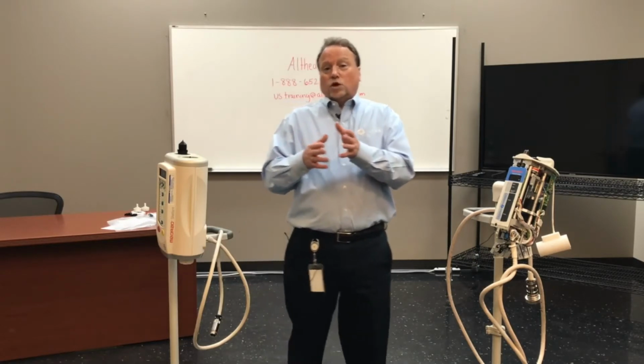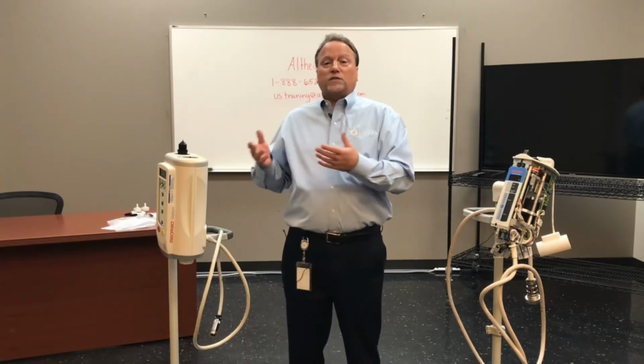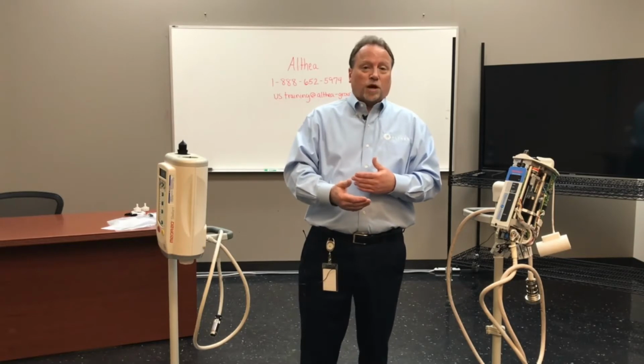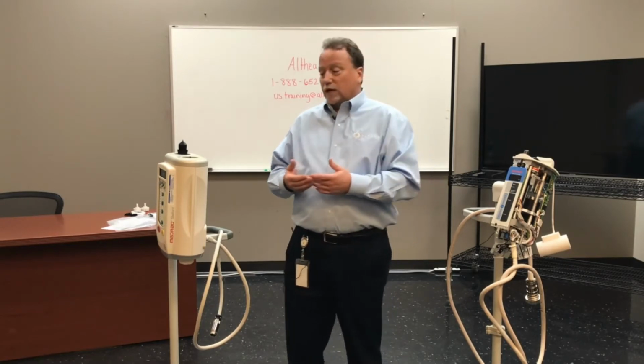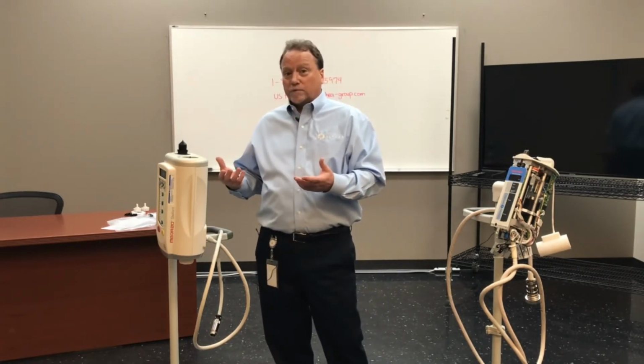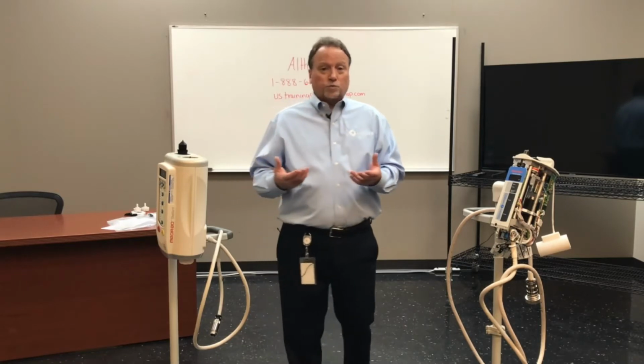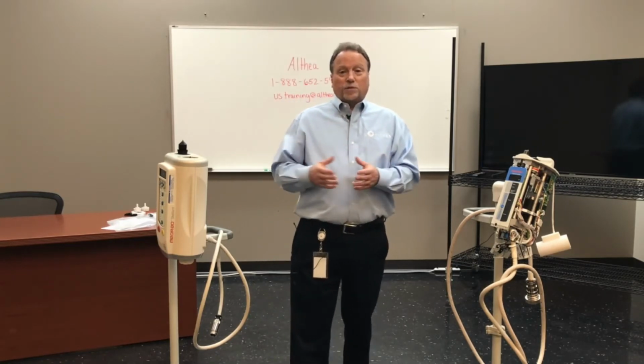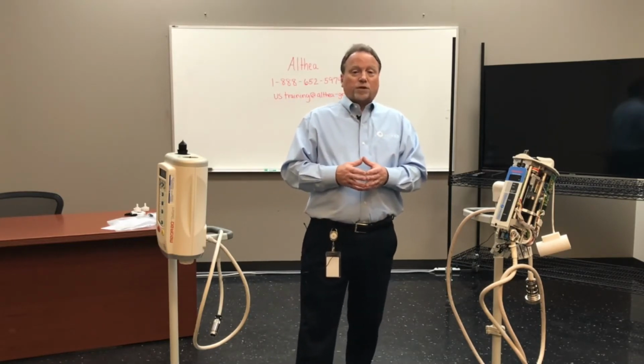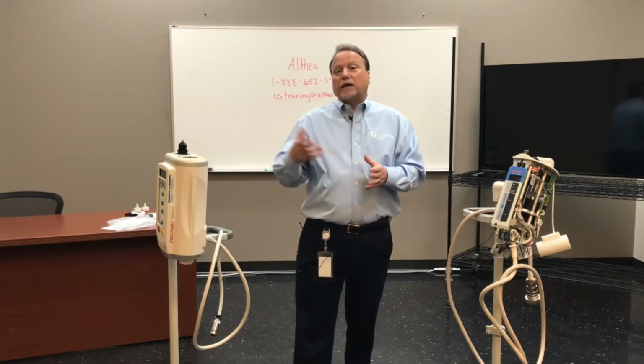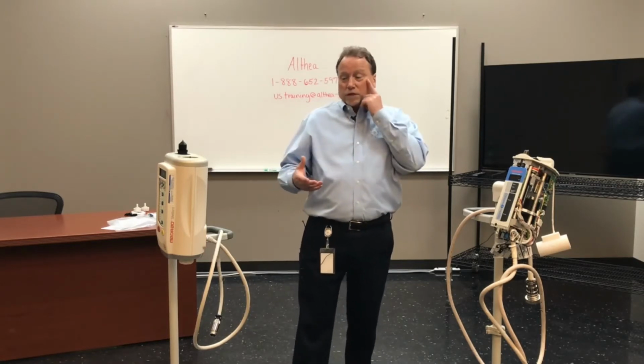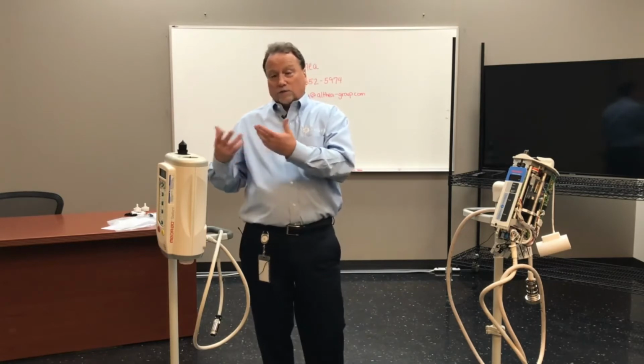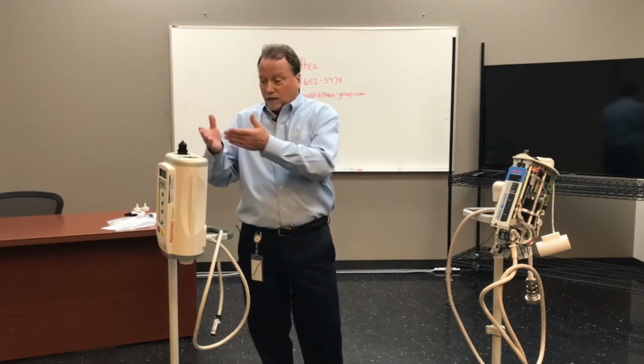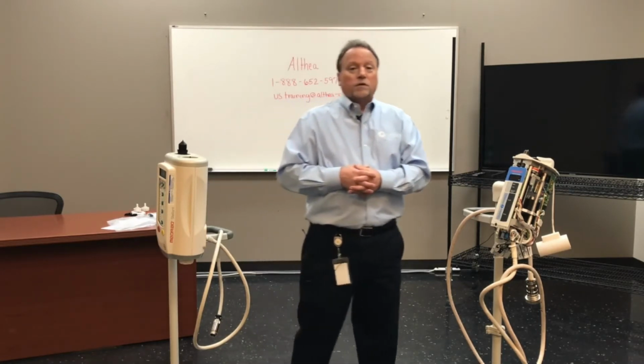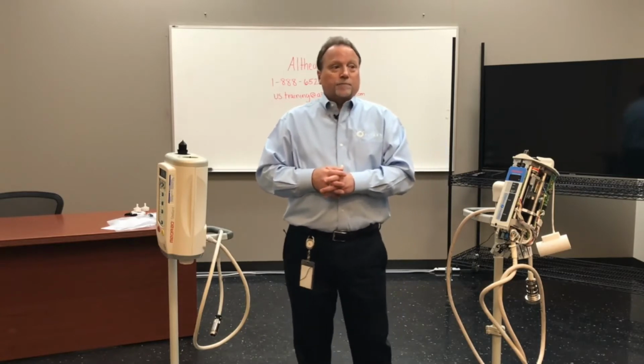Now, since you already started the PM, you can investigate what could be causing this problem. Doing that, you may find a broken or loose spring causing that intermittent issue. That would be something you annotate on your PM to come back and correct, because that wasn't seen prior. That's not a visual issue. You can't say, hey, this is broken.